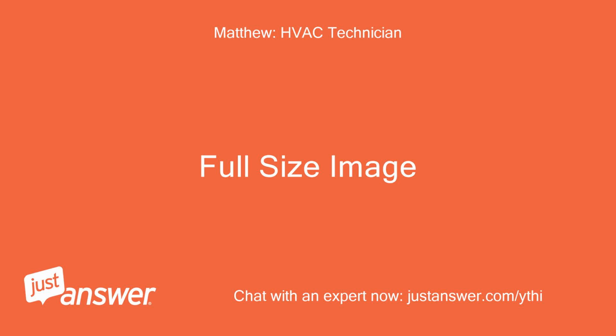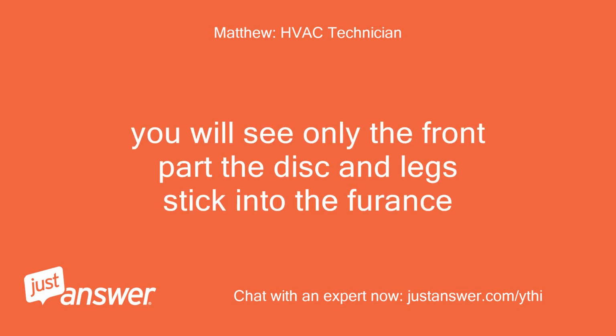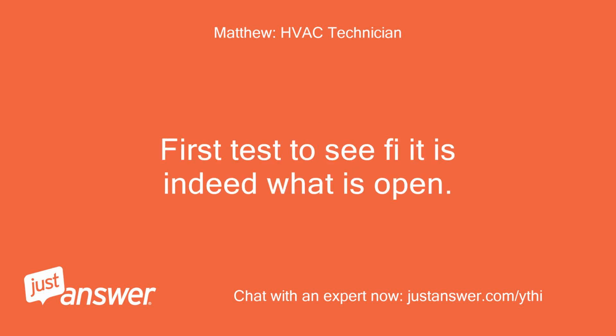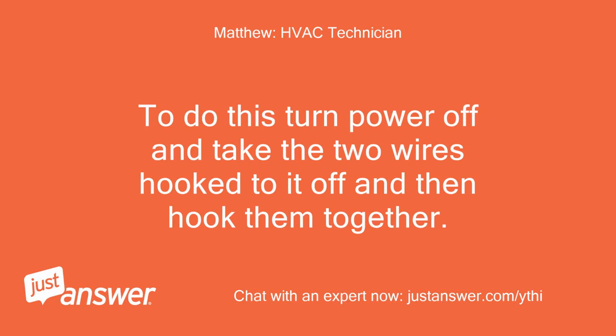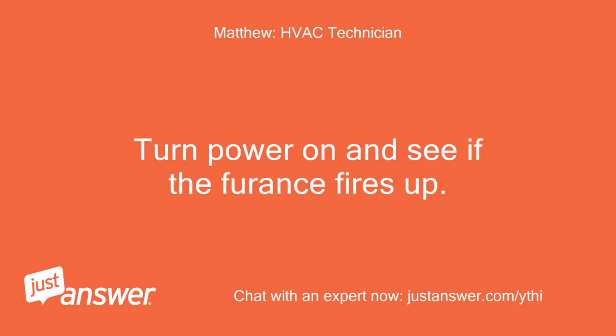Full-size image. This is the limit. You will see only the front part, the disc and legs stick into the furnace. First, test to see if it is indeed what is open. To do this, turn power off and take the 2 wires hooked to it off and then hook them together. Turn power on and see if the furnace fires up.